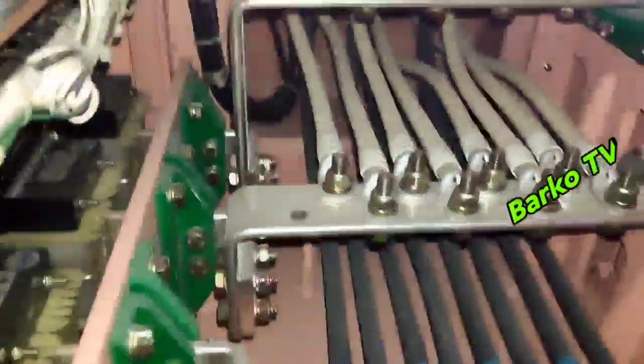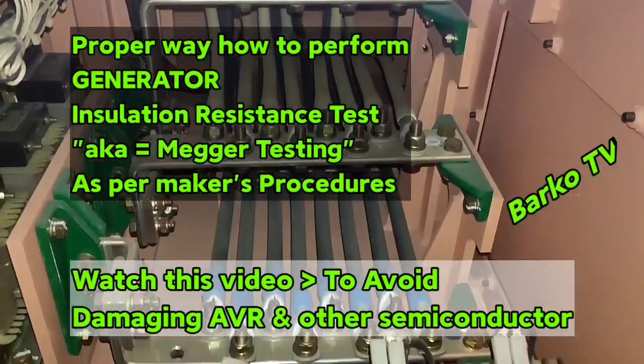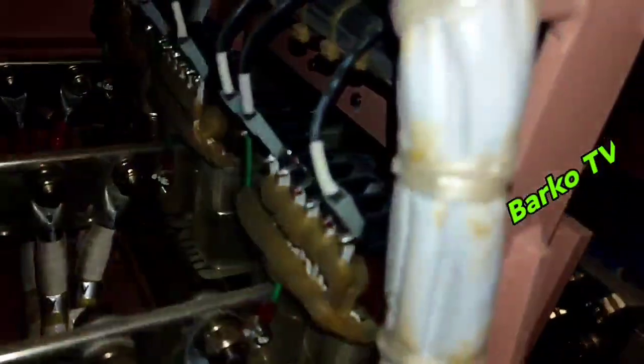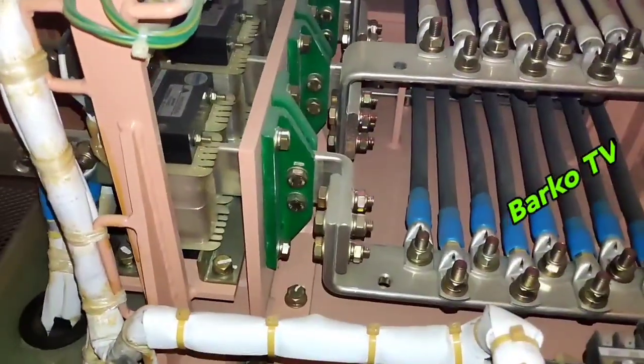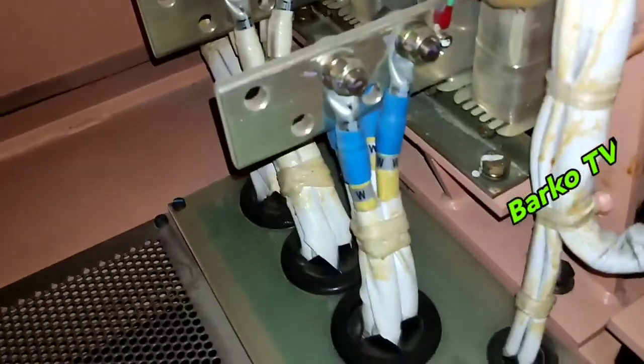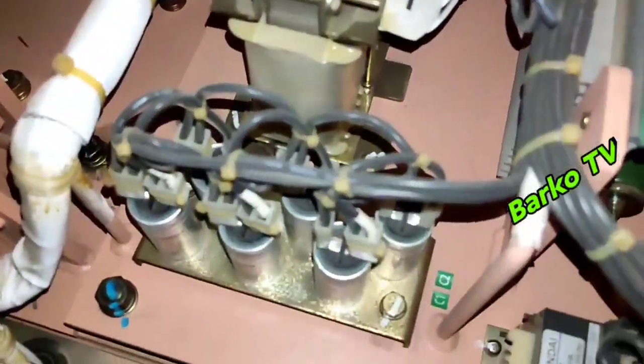Good day. Our topic for today is insulation resistance testing, or megger testing in layman's terms, for our generator. This is a critical and important job. If you don't follow the right procedure as per the manual, it may cause malfunction or worse — it can damage the semiconductor parts of our alternator. I just received an email from a follower that after carrying out an insulation resistance test, the generator had no output, meaning it malfunctioned.